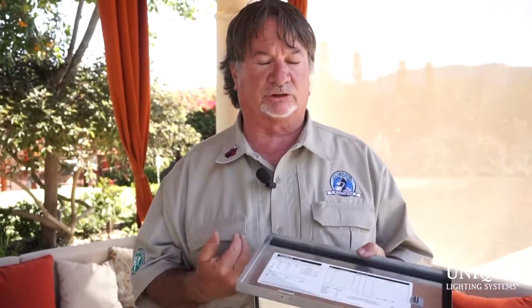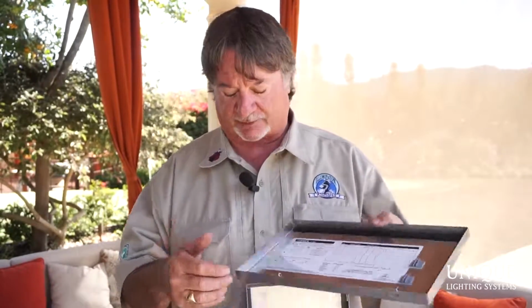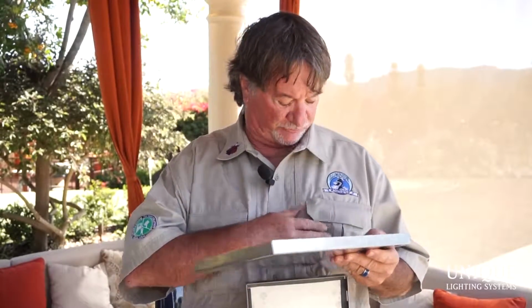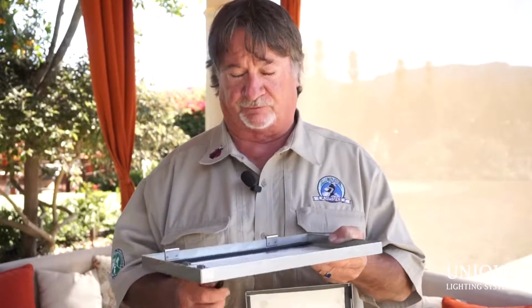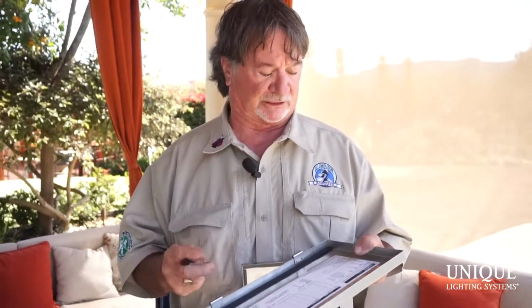The power companies fluctuate their voltage up and down, sometimes as much as 10, 12, 13 volts. So if I'm adjusting my voltage in the daytime and I've got 12 volts at the hub, but come back later and have 13 or 14 volts at the hub, I need to check and verify my primary voltage, because it may very well have increased to 125 or 130 volts. Now I know whether it's a problem that I've done, or a problem with the transformer, or a problem with the power utility company.